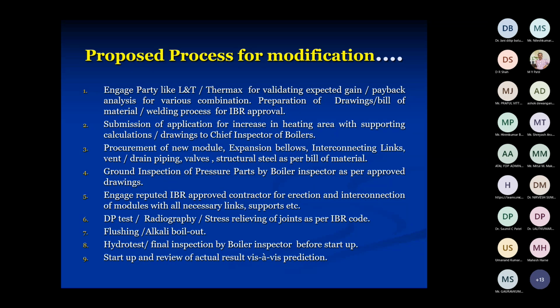Then we engaged an IBR approved contractor, because we cannot engage our regular fabricator or erector for this type of job. We engaged the IBR approved contractor for erection and interconnection of modules with all the necessary links and supports. DP test, radiography, stress relieving, all the procedures as per IBR code were followed. When we received the module, we could not feed it directly into the boiler. It is to be flushed, then alkali boil out. We have to precipitate the boiler, and for that there is one procedure known as alkali boil out. Then hydro test and final inspection by the boiler inspector were carried out after completion of work before startup. Then at startup, a review of actual results was carried out.